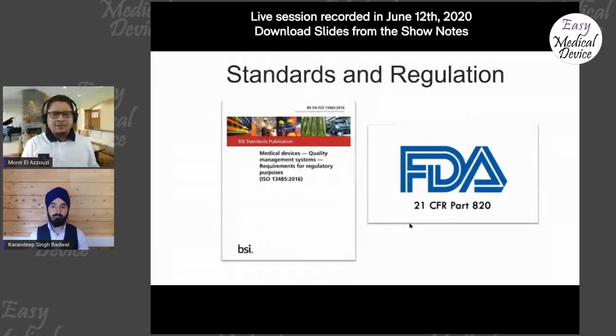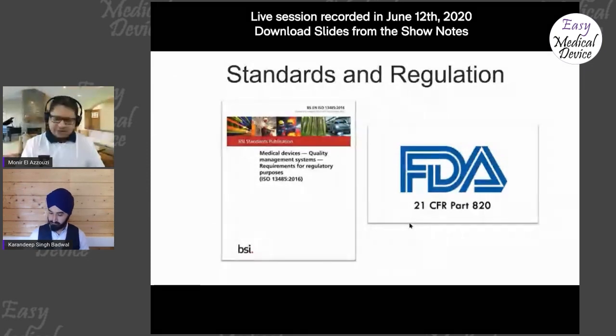For the FDA, for example, I'm using a tool with my teams, which is the QSIT. I don't know if you know this tool. It's a guide or a document, which is the Quality System Inspection Technique, QSIT. And there is a specific chapter. I mean, there is a chapter for everything, but there is one chapter for corrective and preventive actions, which is telling you what kind of questions an inspector, an FDA inspector, should ask you, what they have to look at.